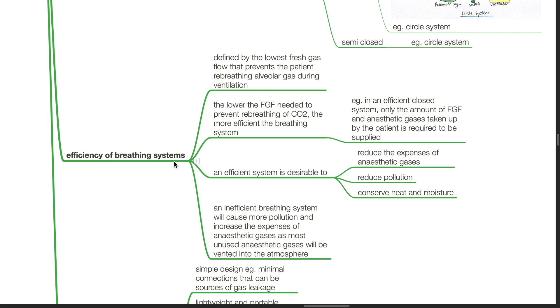Efficiency of breathing systems. This is defined by the lowest fresh gas flow that prevents the patient re-breathing alveolar gas during ventilation. The lower the fresh gas flow needed to prevent re-breathing of CO2, the more efficient the breathing system.